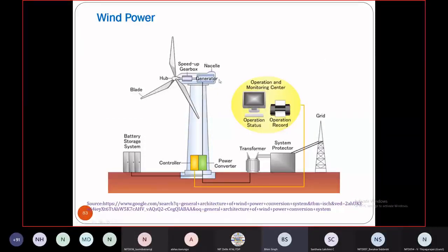So wind is another one, and I told you why. What is the configuration? You have a wind turbine, then you have a generator with a gearbox. Other than the conventional synchronous machine, the salient pole synchronous machine can be designed with a higher number of poles to be directly connected without gear, or a permanent magnet machine can also be designed with a very low speed, on the order of 50 to 150 RPM, which is the wind turbine speed. But all other machines normally need the gear.